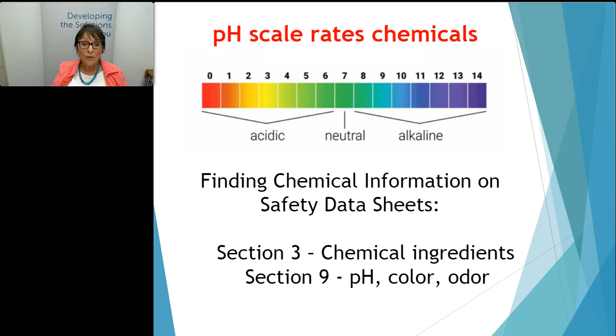So many of you are probably familiar with the pH scale. From 0 or 1, roughly up to about 6 is considered acidic. From roughly about 6.5 to 8.5 is generally considered neutral, at least in the world of detergents and instrument processing, 6.5 to 8.5. And then 9 and above is considered alkaline detergent. So where do you find this chemical information? You might find some of it on the label, but the vast majority of the information will be on the safety data sheet. So you're going to look in section 3 for chemical ingredients, and you're going to look in section 9 for pH, color, odor, etc. So you need the safety data sheets, and you need to make sure they're the current safety data sheets and that you have the correct name and the correct product.